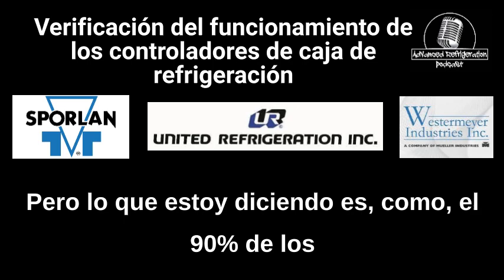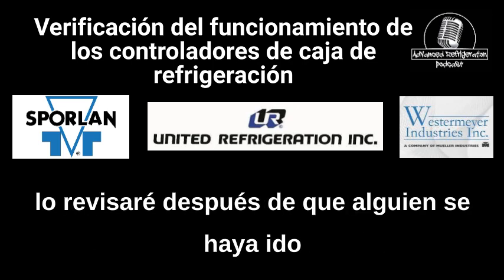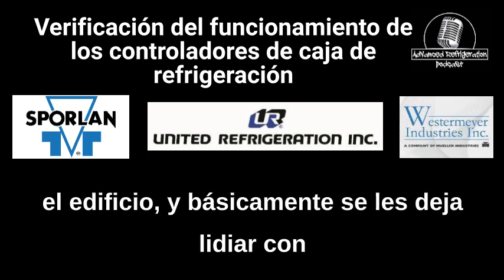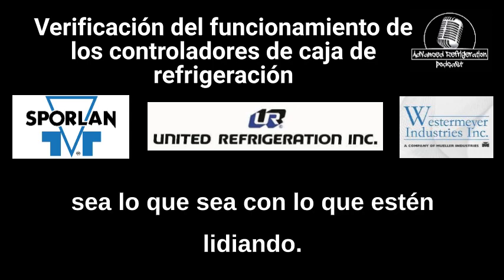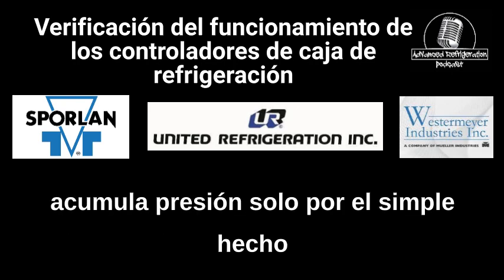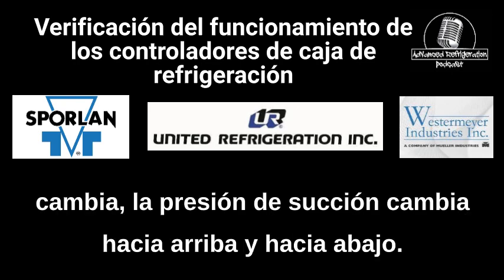But what I'm saying is 90% of the time, the service guys that are listening here are going to be checking it after someone has left the building and they're left to deal with whatever they're dealing with. I would rather shut off the suction and let it build up pressure, just for the simple fact that I want to see it without the variable change, the suction pressure changing up and down. I want to see it steady.